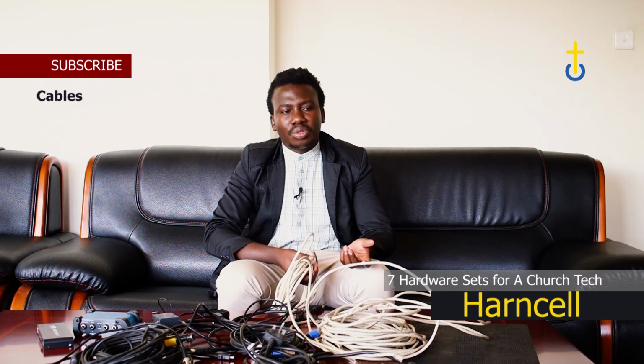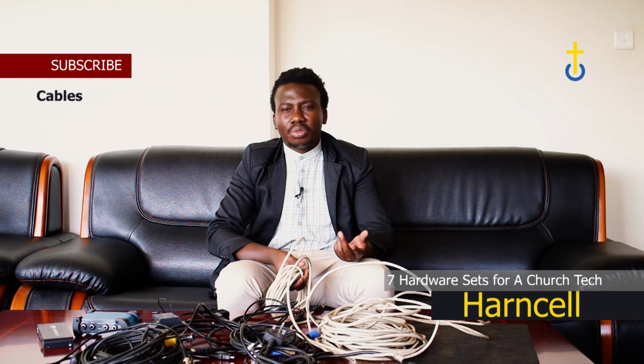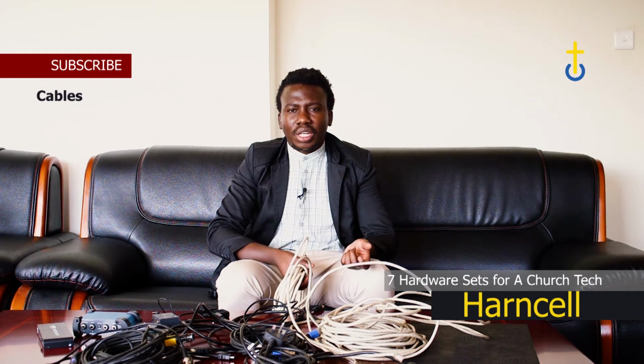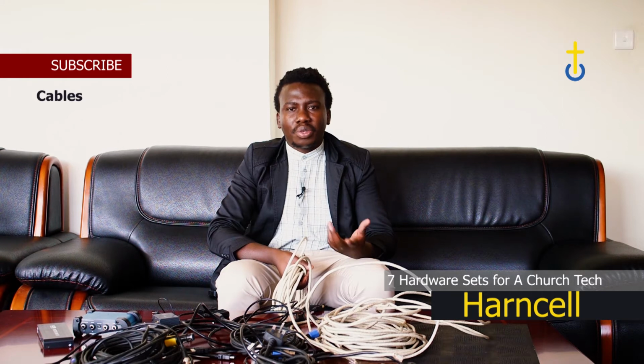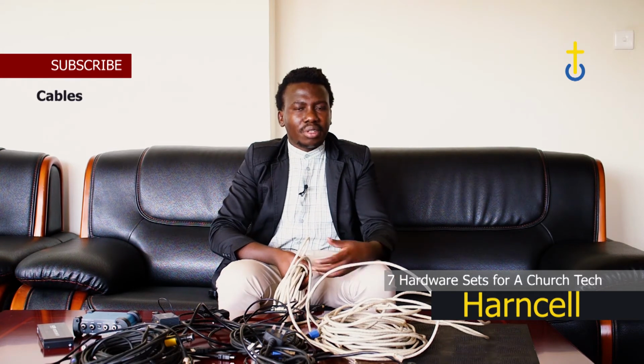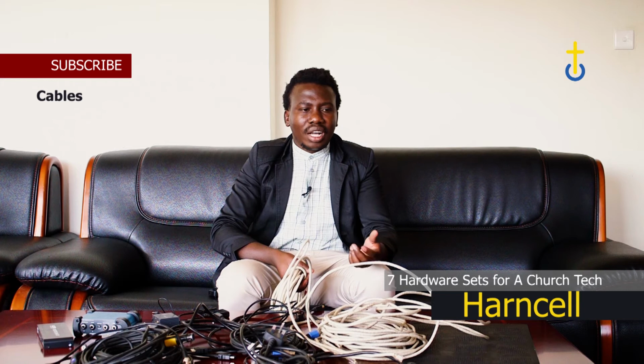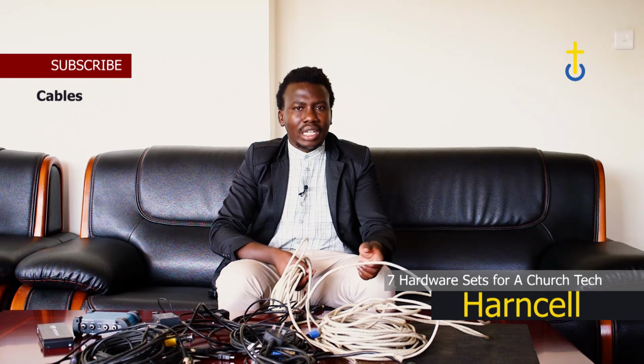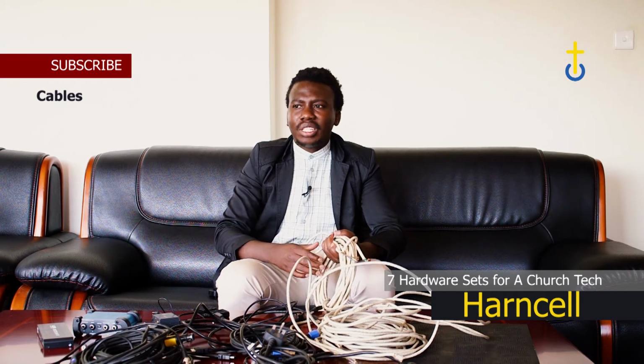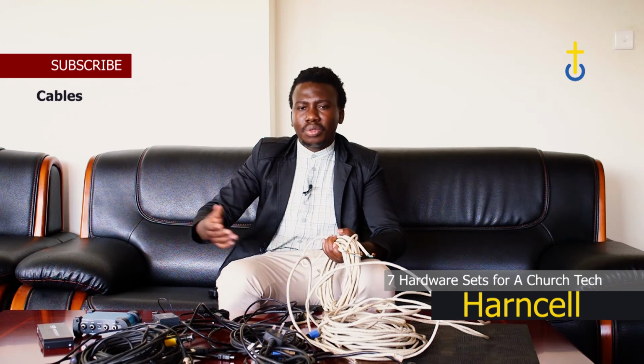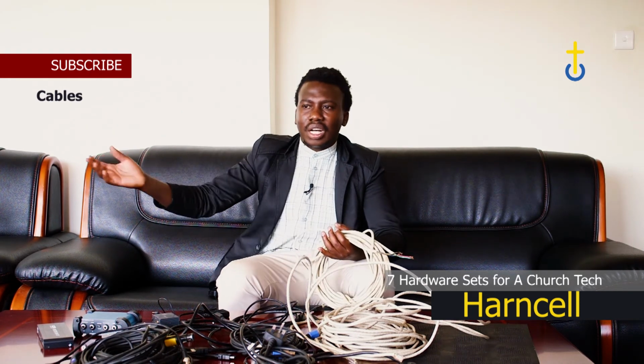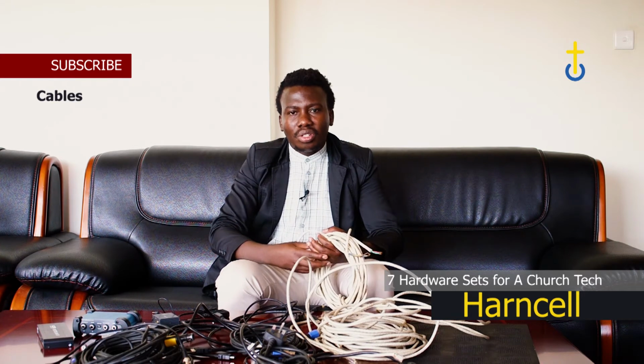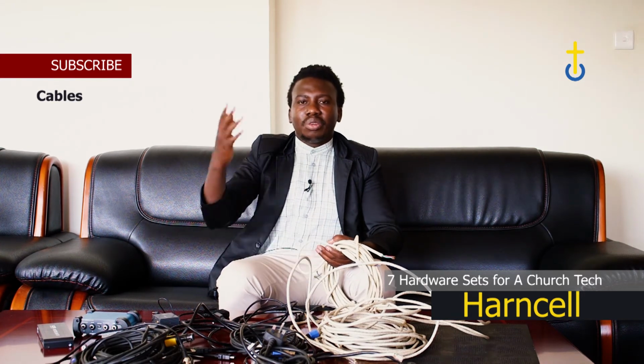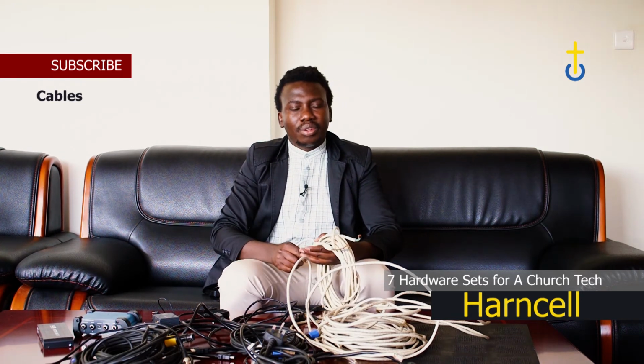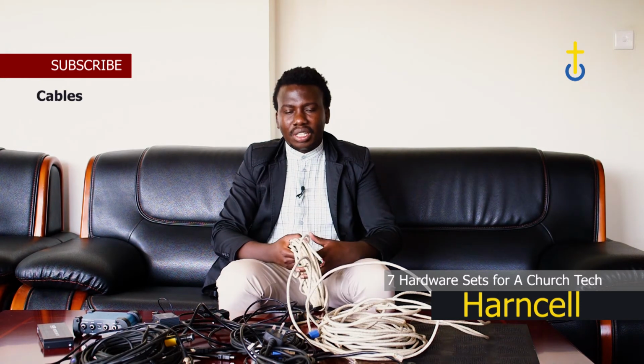For example, the 2.0 and 2.5 cables are mostly used for powering sockets. The 1.5 are used mostly for lighting and other smaller appliances. The bigger ones like the 4.0 and the 6.0 are used for heaters and cookers, and then as you go on, other larger cables are used for supplying power to the premises and for distribution.